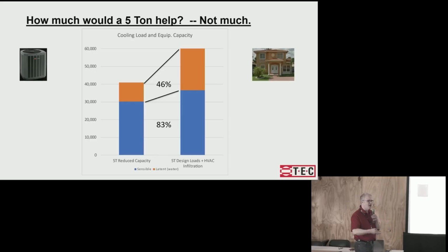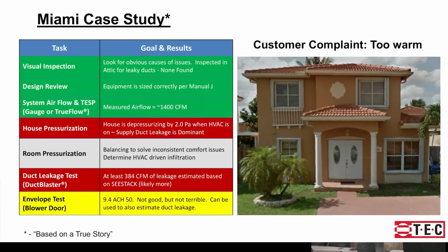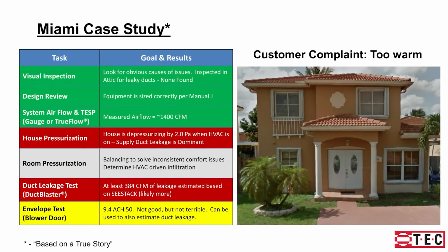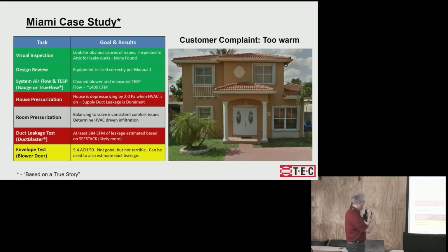So putting in the 5-ton will only help slightly, because of the leak. The message here is you've got to find the leak and fix the leak to improve the situation. So bottom line here, we want to start a conversation about what these tasks are. What should you be measuring to try to get to the bottom of it? I don't think we really know what order is best for these, and it probably depends on the situation. It probably depends on what kind of houses you're dealing with. But these are some things that you should be measuring and doing to try to get to the bottom of a problem house.